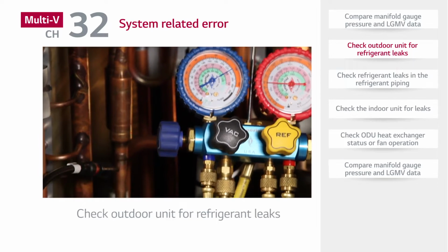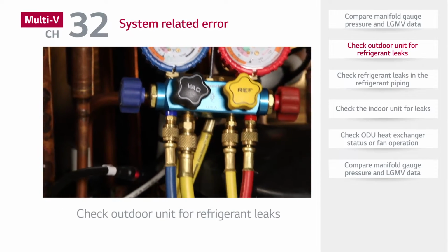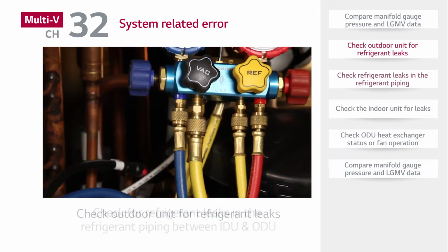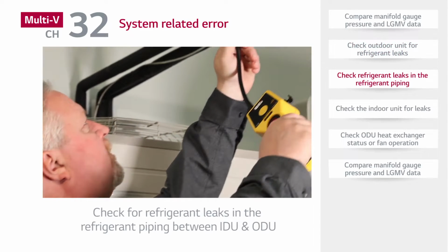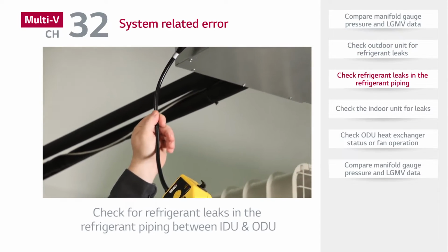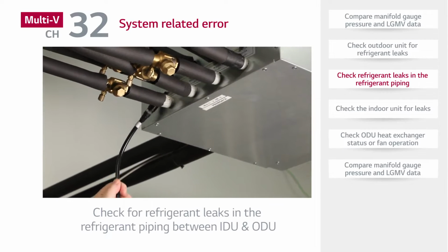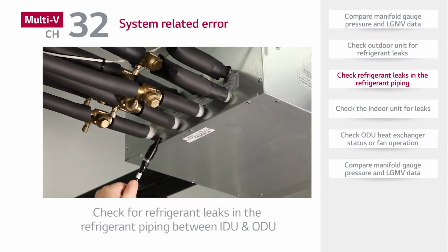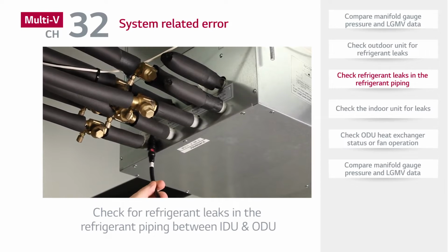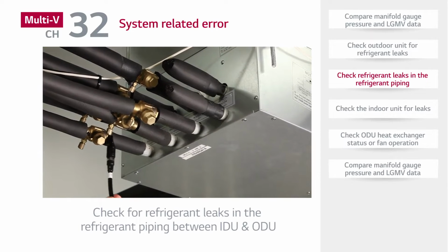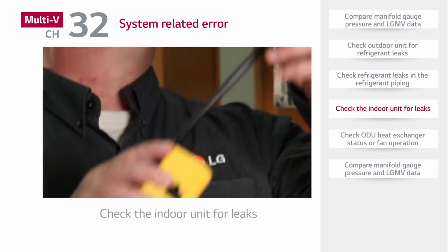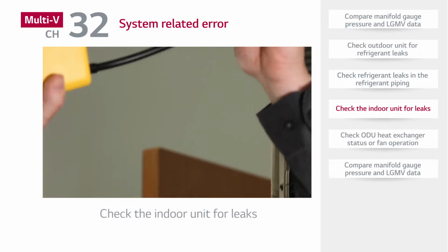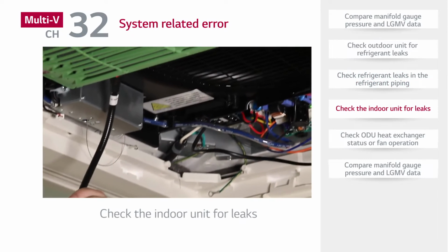If the refrigerant level is low during heating operation, a CH151 error may occur. Next, check for refrigerant leaks in the refrigerant piping between the indoor unit and outdoor unit. If there are no leaks in the refrigerant piping, check the indoor unit for leaks.